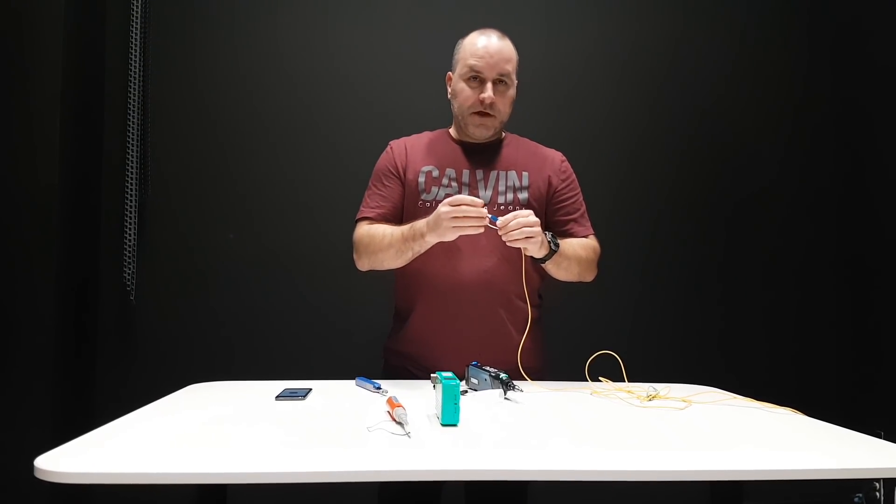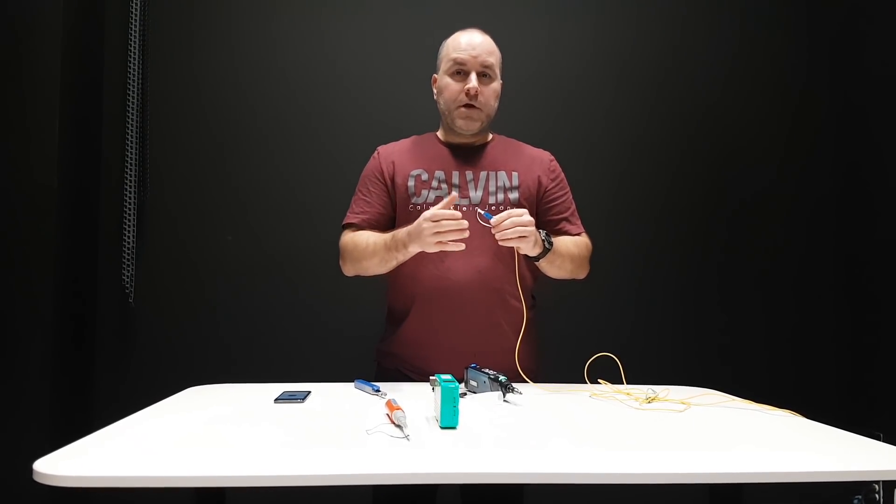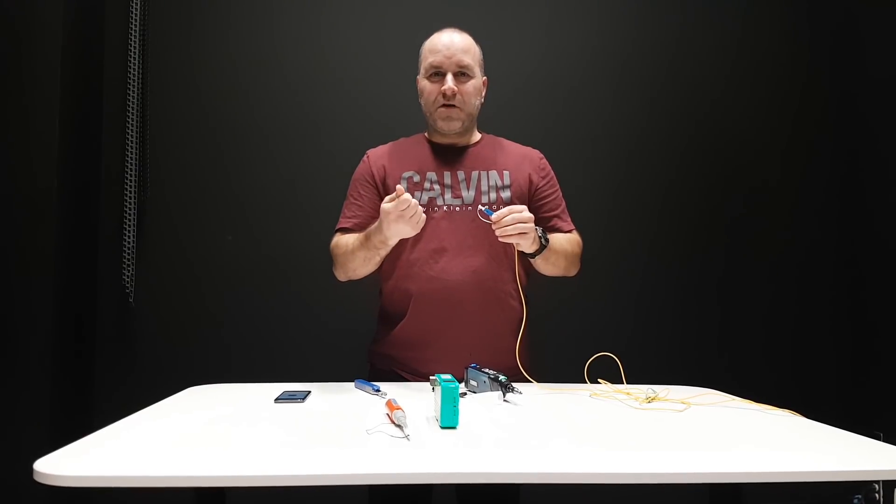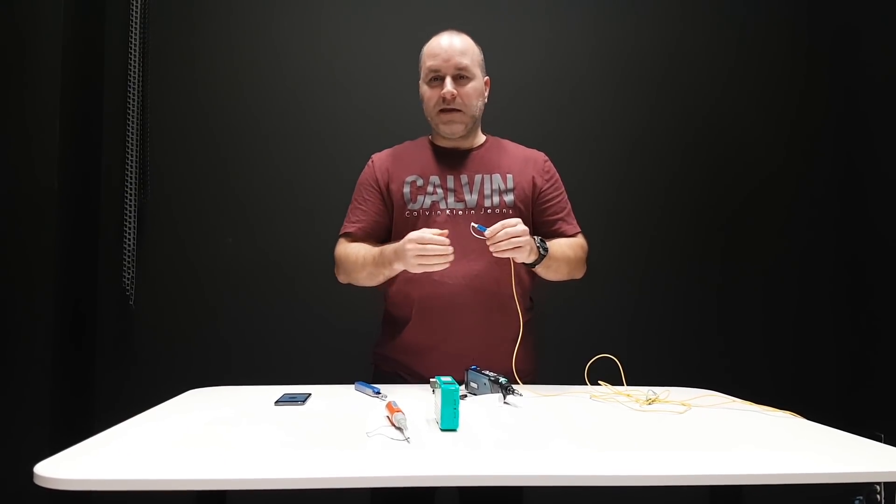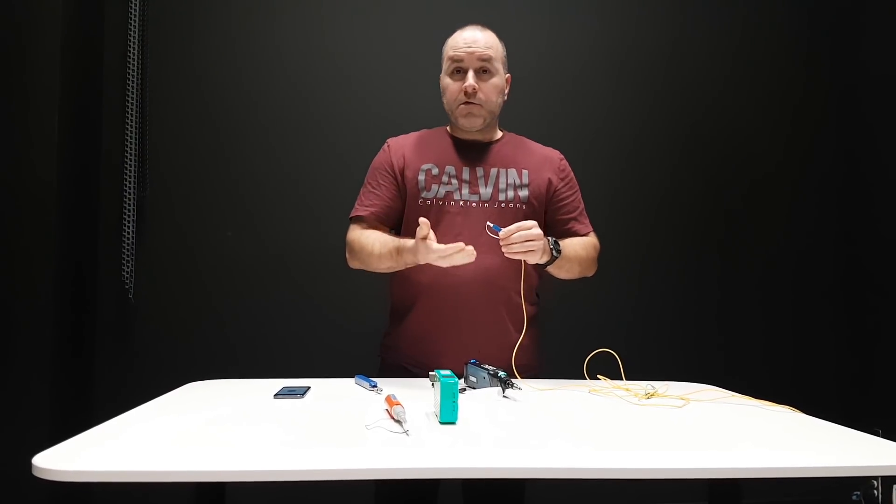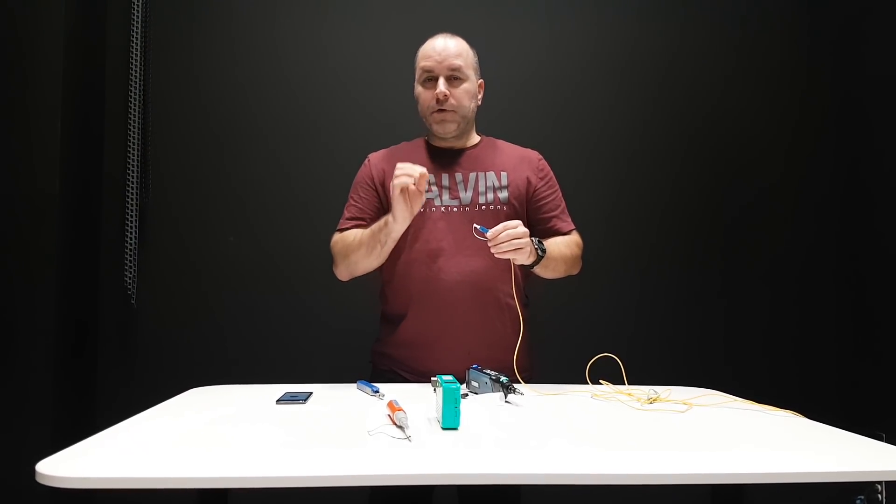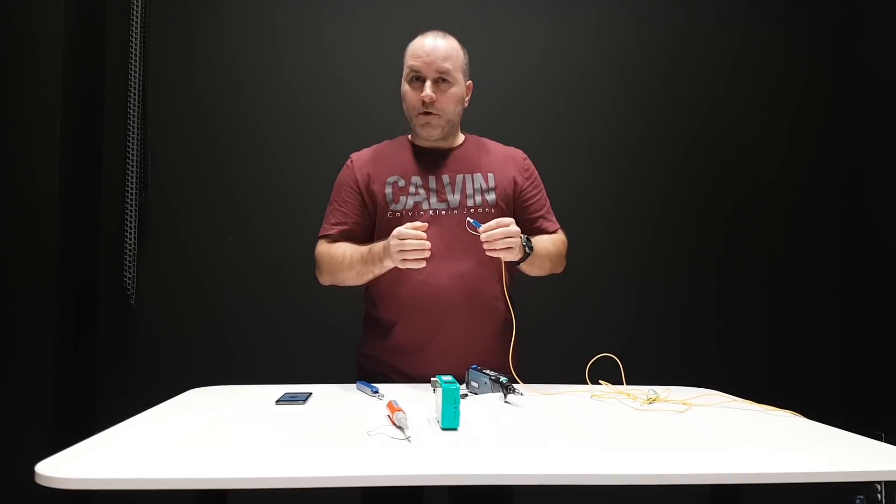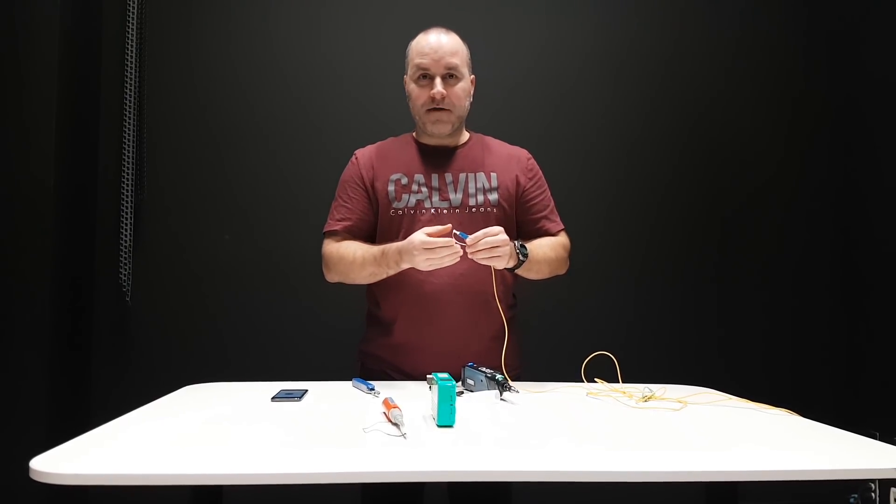The wet wipes will be used when you have really tough dirt to get rid of. You've got embedded crusty dirt on your connector, and even 20 clicks of this will not work. You can use the wet wipes, but what is really important is when you use the wet wipes, you need to dry it off afterwards.